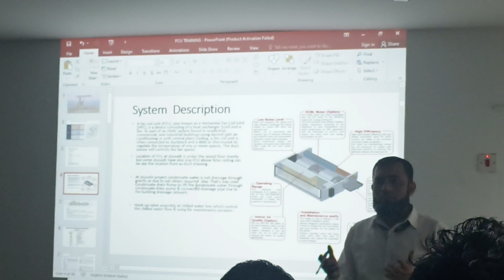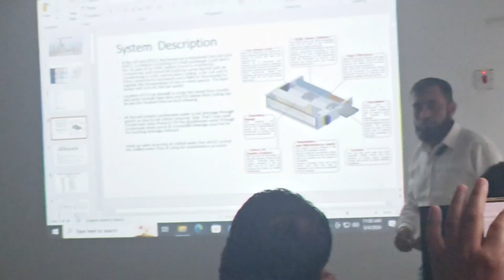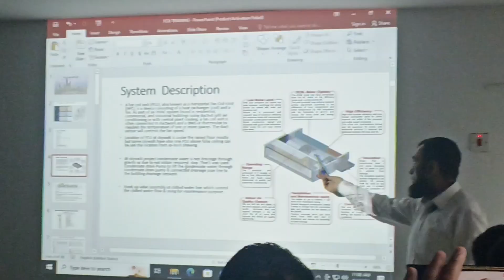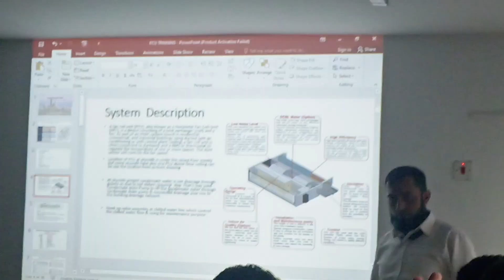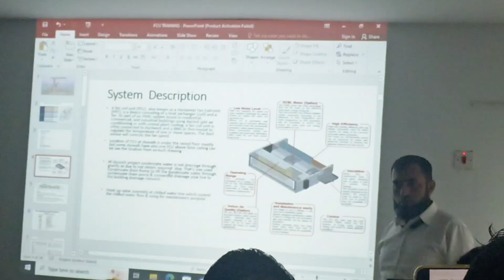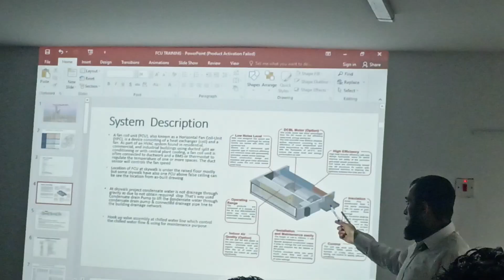This is just the function. If you see here, this is the blower fan, operating through one motor - centrifugal fans. The fan has 3 speeds only, as you already saw - low, medium, high. Here we have the fan coil, which has 4 row, 3 row, 5 row, 6 row configurations depending upon their design. I will show you how to understand the row.